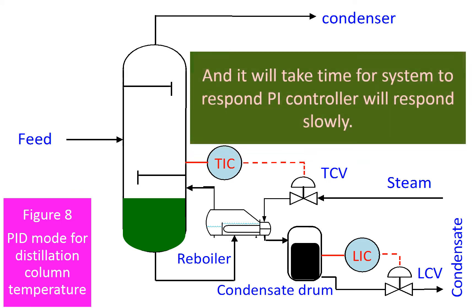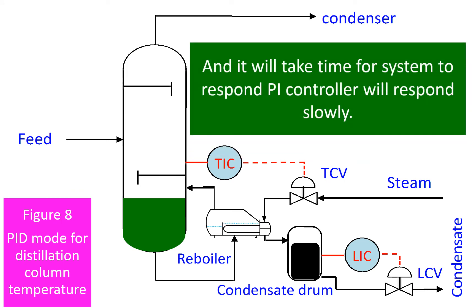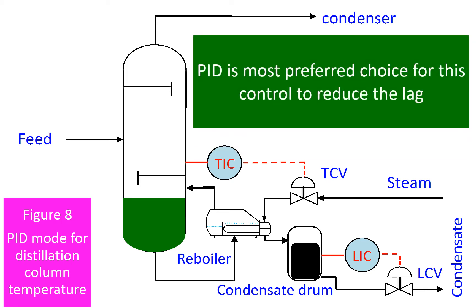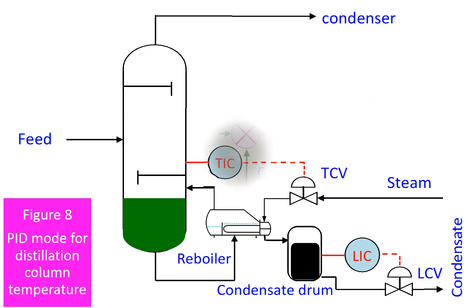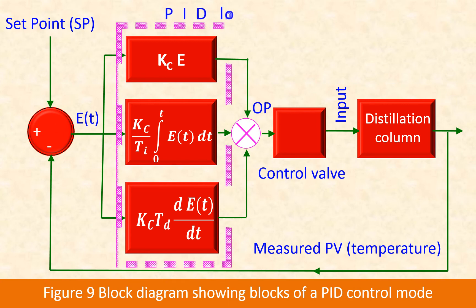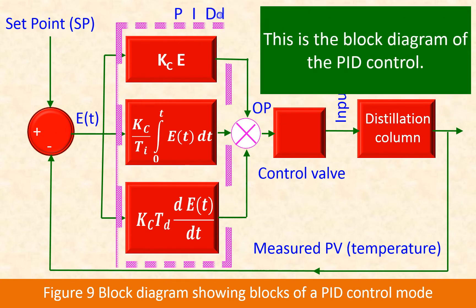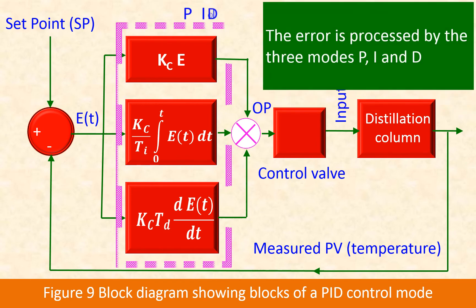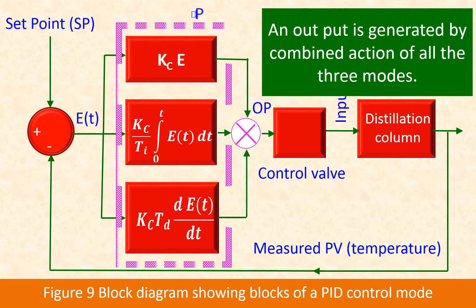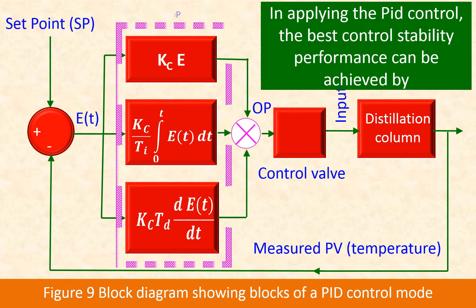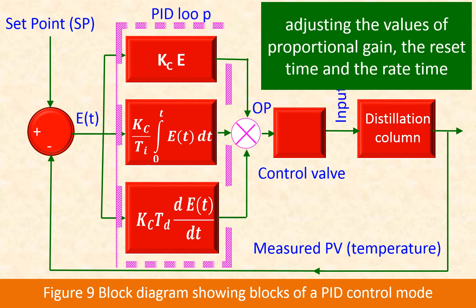PID control will respond to this slow process, and PID is the most preferred choice for this column control to reduce the lag. This is the block diagram of the PID control — the error is processed by the three modes P, I, and D, and an output is generated by the combined action of all three modes. In applying PID control, the best control stability performance can be achieved by adjusting the values of the proportional gain, the reset time, and the rate time.